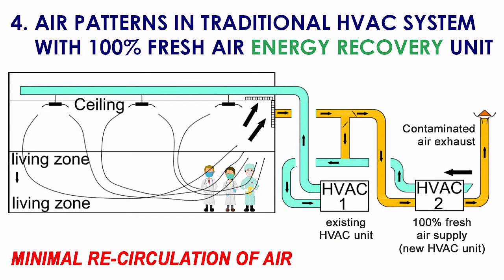Let's now look at the air pattern in a traditional HVAC system with a 100% fresh air energy recovery unit. Here we can see the traditional HVAC unit, and unit number 2 is a 100% fresh air unit. Both installations are integrated, and a very important piece of duct is this duct, where we have 2 dampers, so you can have the fresh air coming in and mix it with a little bit of return air. So we can choose a very high percentage of fresh air coming in and going to the living space to the ceiling diffusers.